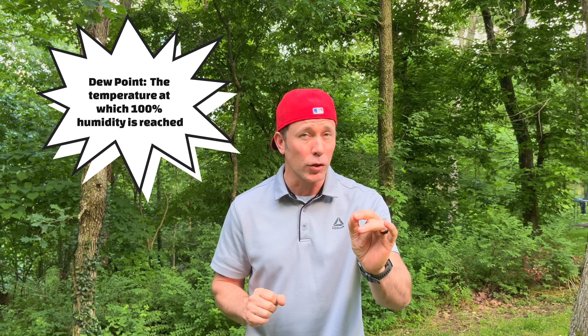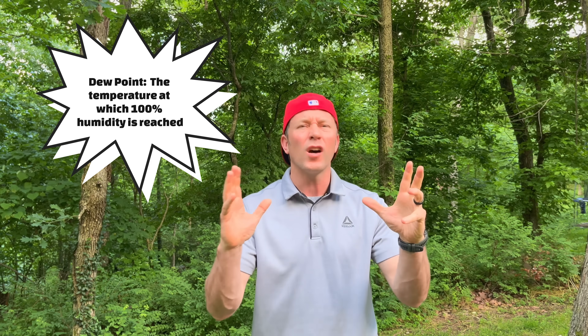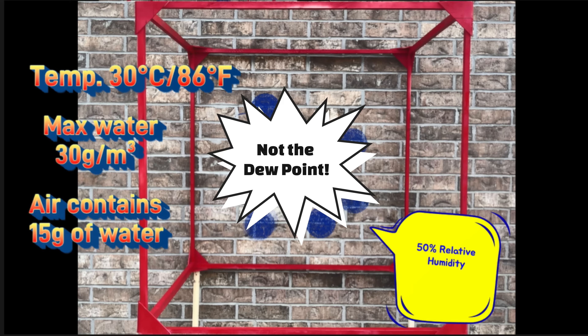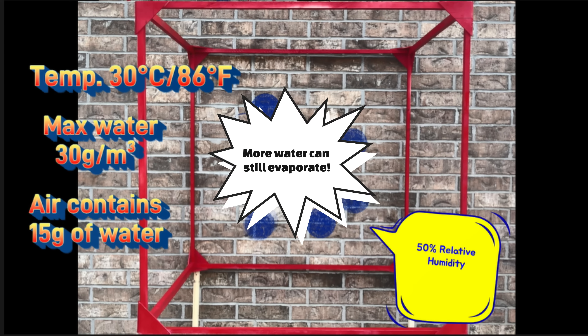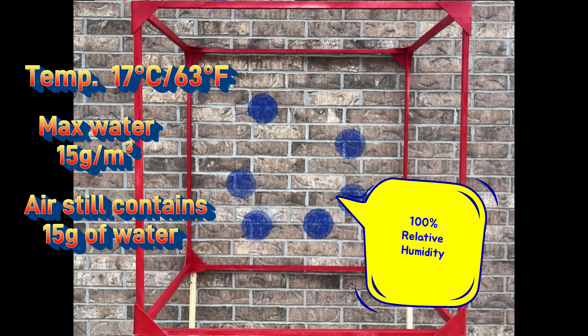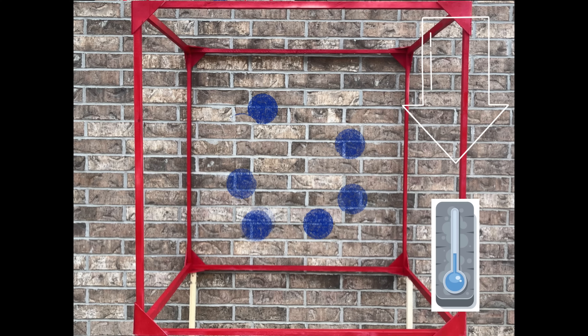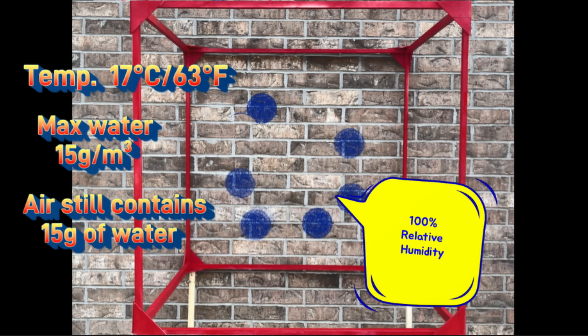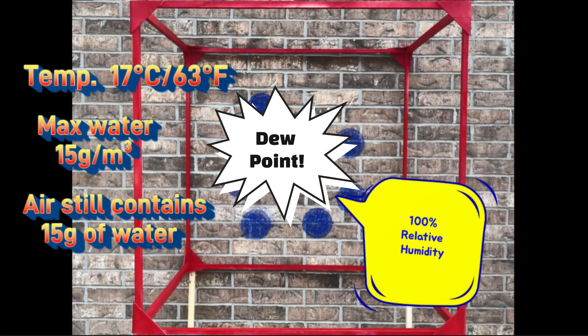Dew point is the temperature at which a particular sample of air reaches 100% humidity, also known as the saturation point. Going back to that 30 degrees Celsius day with 50% humidity and 15 grams of water in the air — at that point, the air sample was not at its dew point, and more water could still evaporate into the sample. But if overnight the temperature started to drop, once it hit 17 degrees Celsius the air would reach its saturation point, since 15 grams of water is all that will stay in the vapor state at that temperature. If the temperature dropped any more, some water would condense and we would wake up to fog or dew. So 17 degrees Celsius would be the dew point for this particular sample of air with 15 grams of water in the vapor state.